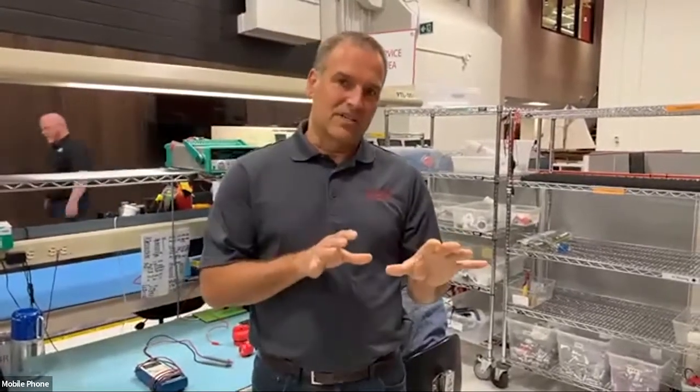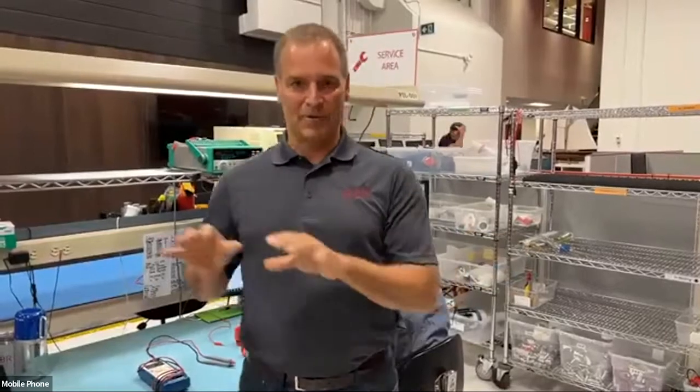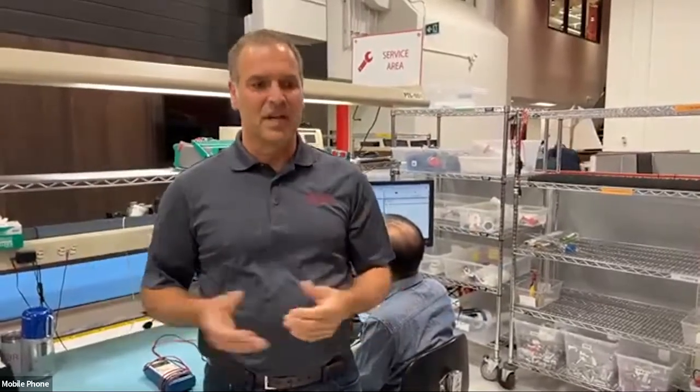So one of the big questions that comes up is, why calibrate? And the short answer is that to maintain datasheet accuracy, we recommend annual calibration. Now, the fact is, sometimes we understand the logistics of getting that done can be challenging, and that's why we introduced our 3-year free calibration guarantee, which takes some of the questioning out of how long it's going to take to get calibration done, because we guarantee 3 weeks or less on standard calibrations for a turnaround time. So today we're going to see how a CTD goes through the calibration process and the elements that are involved.